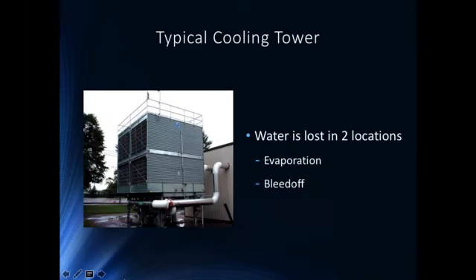And so a tremendous amount of water is evaporated out of these systems. The second source of loss is basically through controlled bleed off. And essentially what we need to do is, as the mineral content continues to rise, we have to remove some of the water to be sure that the minerals do not deposit, therefore costing us energy, not letting the systems last as long as they should, etc. So two primary places that water's lost, one through evaporation and one through bleed off.